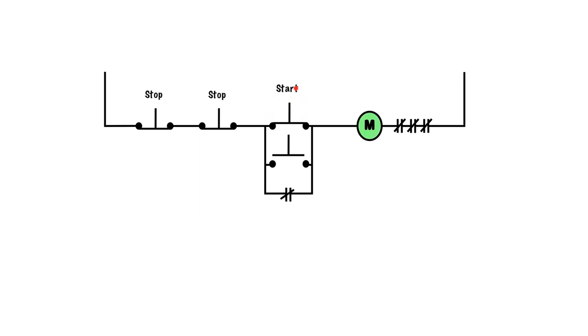If I press down on the first start pushbutton, power can come through to here, energize the contacts here, or energize the coil M through their normally closed overloads and energize these sets of contacts or seal in the contacts.